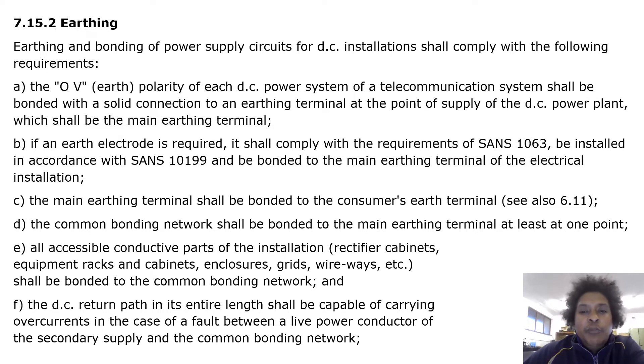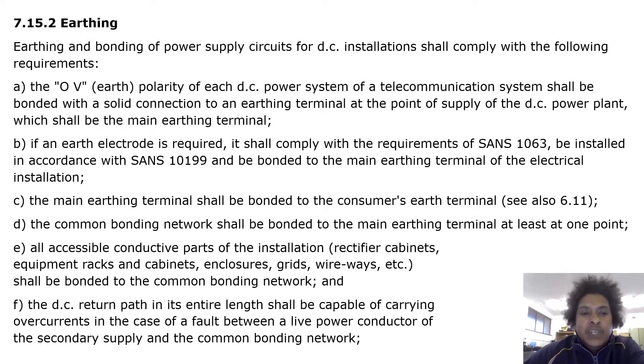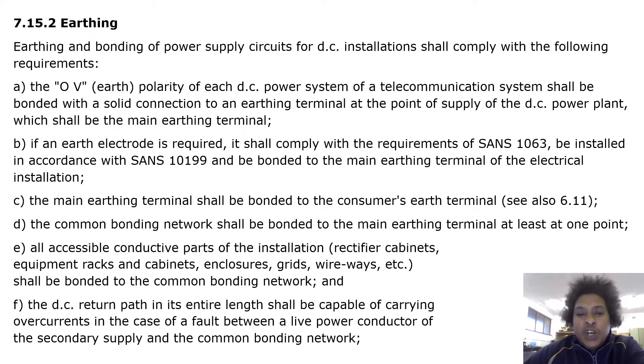If an earth electrode is required, it shall comply with the core requirements of SANS 1063, be installed in accordance with SANS 10199, and be bonded to the main earthing terminal of the electrical installation. The main earthing terminal shall be bonded to the consumer's earth terminal. The common bonding network shall be bonded to the main earthing terminal at least at one point.